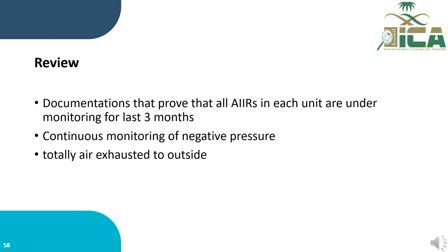We need to review the documentation that proves that all airborne infection isolation rooms in each unit have been under monitoring for the last 3 months, to ensure continuous monitoring of negative pressure and that the rooms are at minimum minus 2.5 Pascal all the time, with air totally exhausted to the outside, 100%, through a high efficiency particulate air filter, what we know as a HEPA filter.